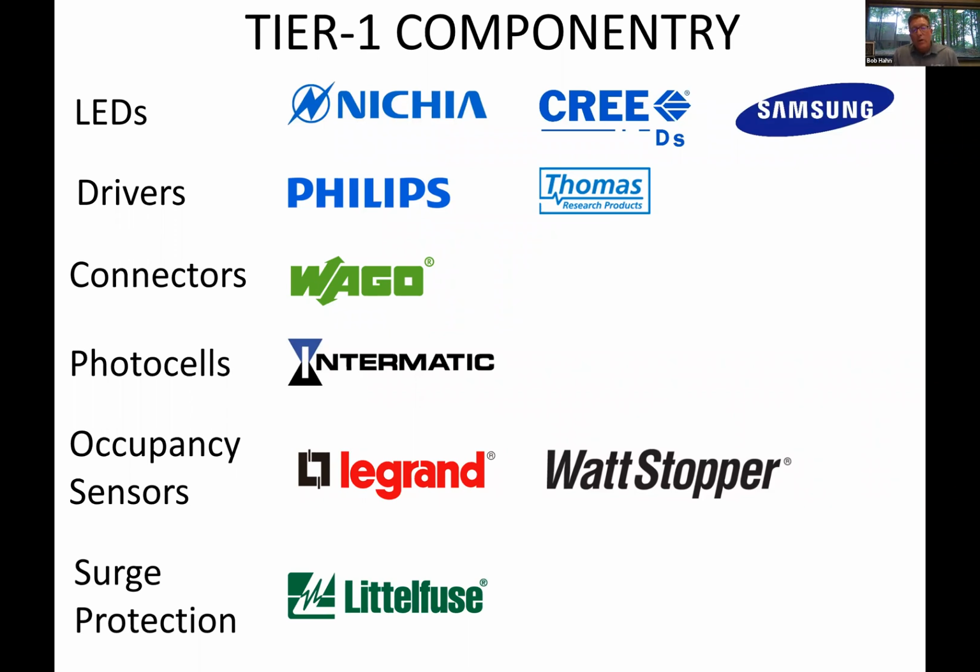When I say indoor, I'm saying like a normal troffer fixture that's in HVAC, and it's usually somewhere around 72 degrees the entire time. So that's what we're seeing a lot of in a lot of less expensive product. Now, the key there is that it actually will be as bright as an outdoor LED for about a year to 2.5 years. And then the swings in temperature and the outdoor corrosion and everything else will start to impact it. And you'll see the product start to begin to dim. So maybe even 1 year, maybe even 2 years in, you might make it with that product. But again, it's going to go down quick after that.